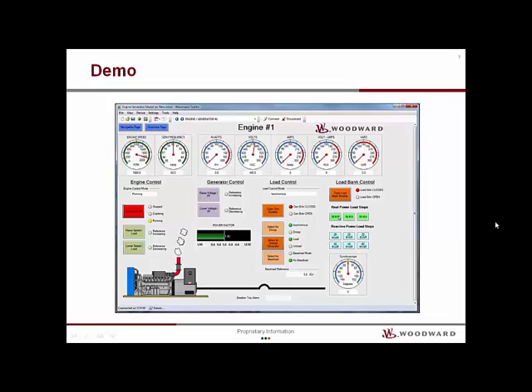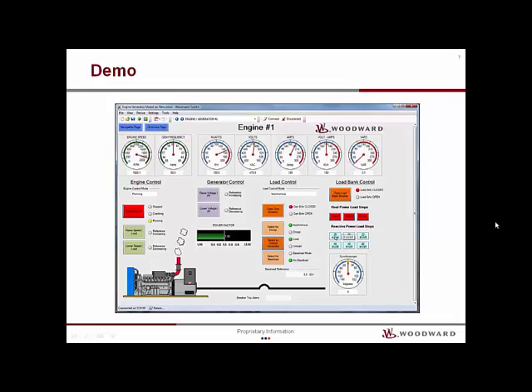I will start by putting resistive load on the generator: 50 kW, then another 50, and the last 50. 150 kW is full load on the generator. Notice that the power factor meter reads a unity power factor of 1.0.